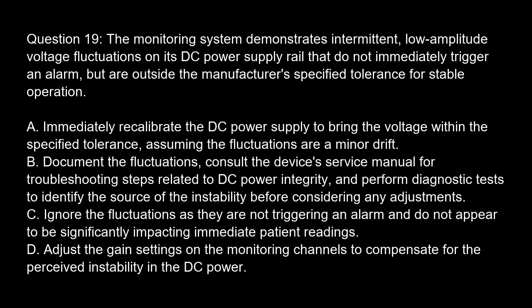Question 19. The monitoring system demonstrates intermittent, low-amplitude voltage fluctuations on its DC power supply rail that do not immediately trigger an alarm, but are outside the manufacturer's specified tolerance for stable operation. Option A. Immediately recalibrate the DC power supply to bring the voltage within the specified tolerance, assuming the fluctuations are a minor drift. Option B. Document the fluctuation. Consult the device's service manual for troubleshooting steps related to DC power integrity, and perform diagnostic tests to identify the source of the instability before considering any adjustments. Option C. Ignore the fluctuations as they are not triggering an alarm and do not appear to be significantly impacting immediate patient readings. Option D. Adjust the gain settings on the monitoring channels to compensate for the perceived instability in the DC power.